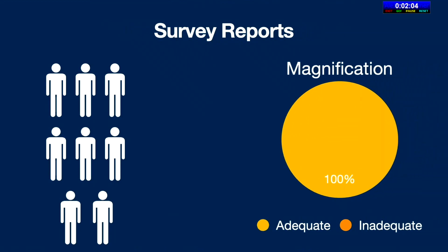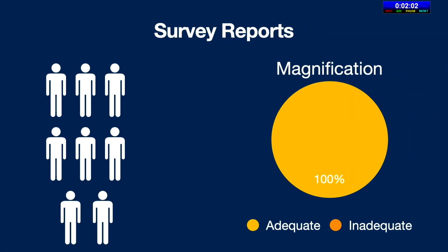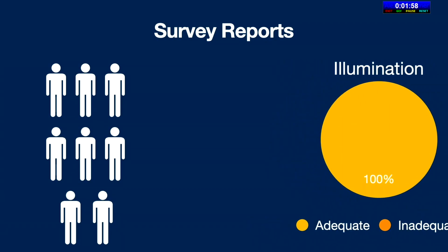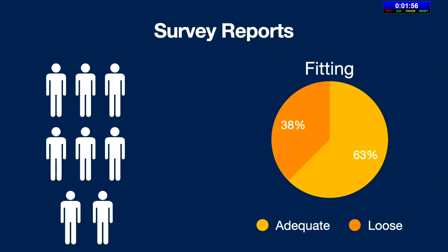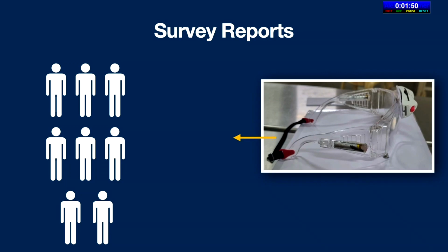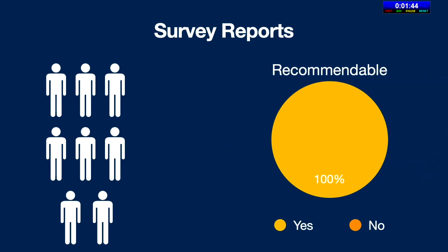All of them reported adequate magnification and illumination. 3 of 8 doctors reported a loose fit of the device. This was then corrected using an elastic band attached to the rear of the frame. All of the users said that they would recommend it to their colleagues.